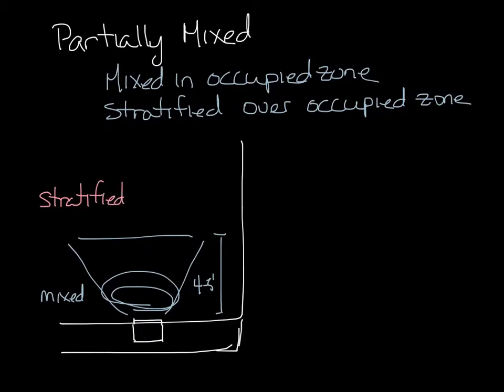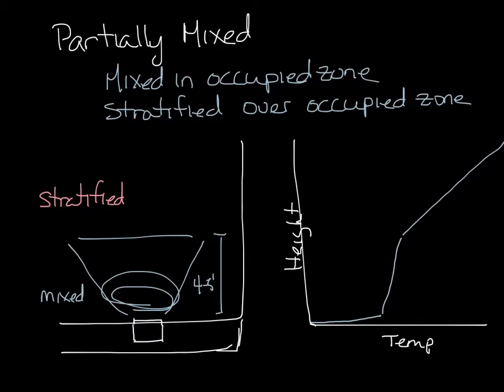Above that height, the air is stratified because the diffuser does not have any velocity in that area. A partially mixed system looks something like this. Right at the floor you'd have a temperature rise because that's where the diffuser is, then you'd have a mixed zone that's fairly flat, and then the stratified layer on top.